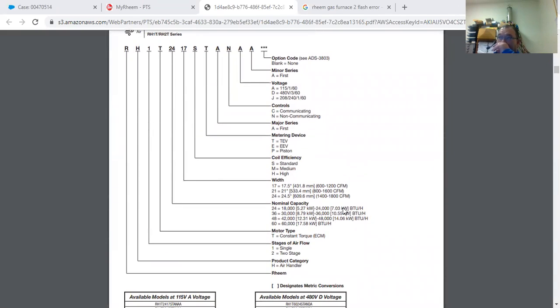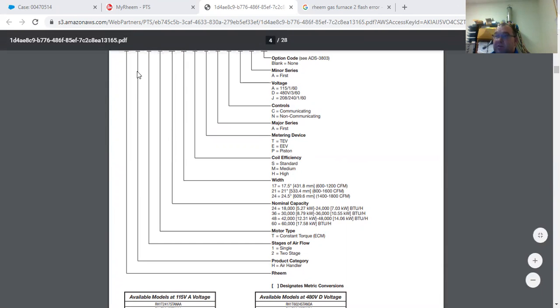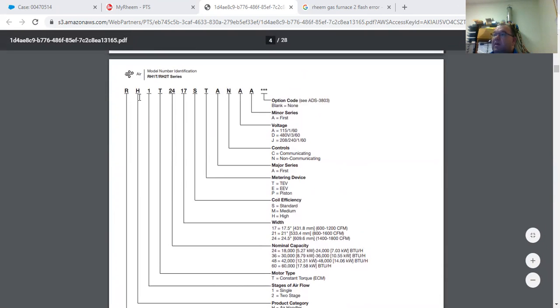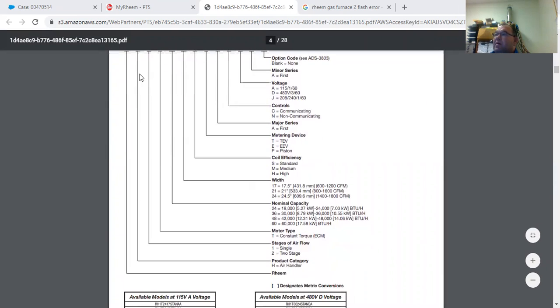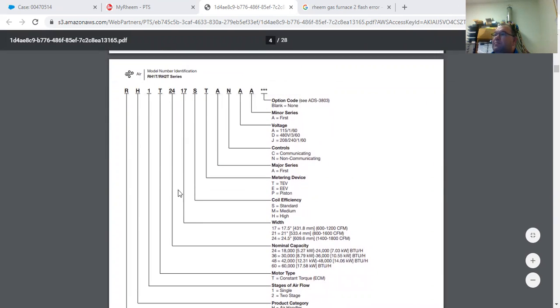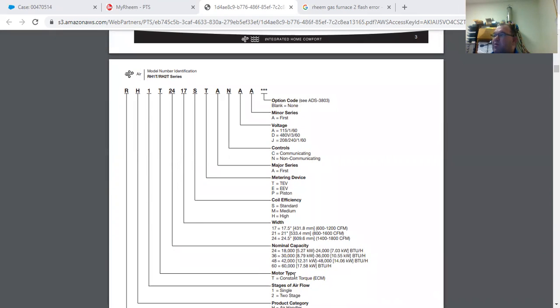We'll go over some nomenclature here so you kind of understand what you're getting. This is going to be your typical model number, just to kind of break this down. The first letter is the R. In this case here, it indicates the Rheem. The H stands for air handler. The 1 stands for the number of stages. In this case here, the T stands for constant torque motor. If you had a V, it's a variable speed. If you have a P, it's a PSC motor.